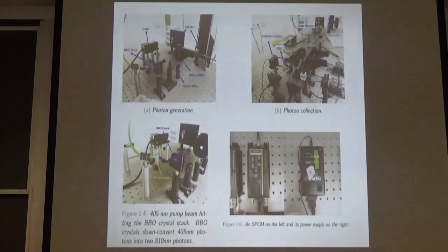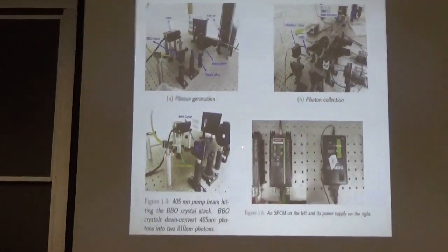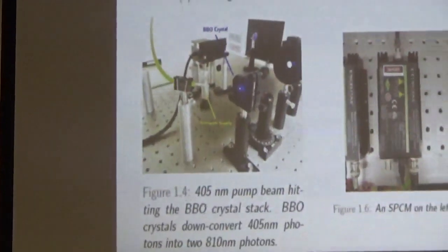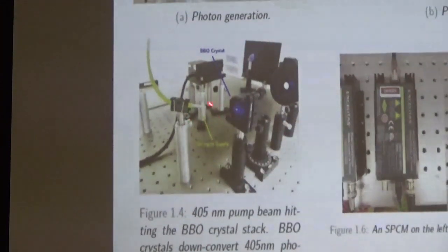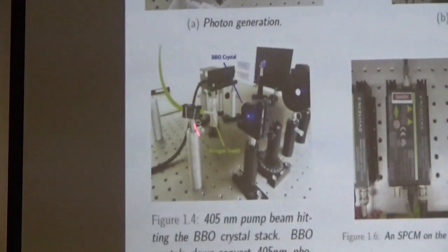We'll get into the details of how it is converting those incoming laser photons into single photons. And then after this, we have this nitrogen supply that's protecting that crystal. So this crystal is hygroscopic. If it gets a lot of moisture, it will be damaged, and it is quite expensive. We want to protect it, so we have a continuous supply of nitrogen over it.